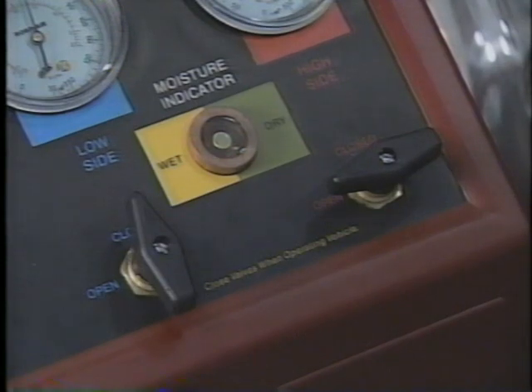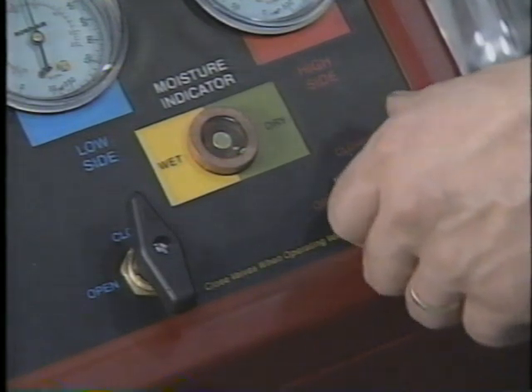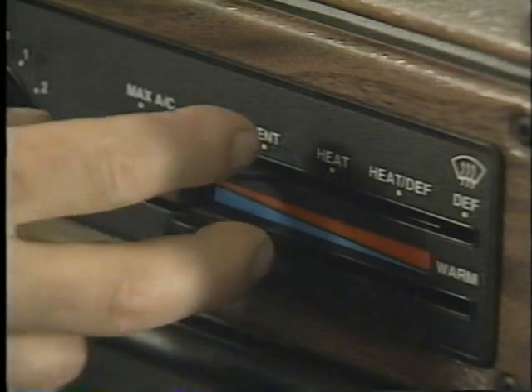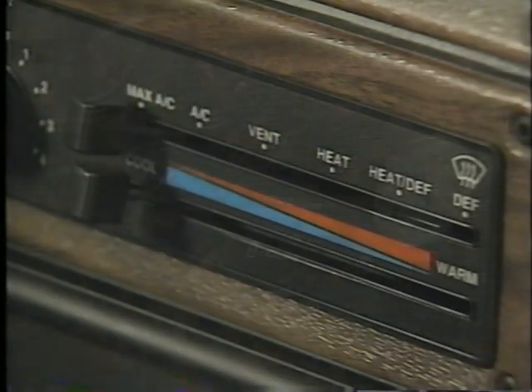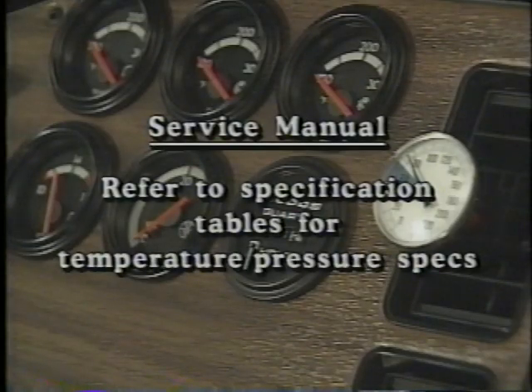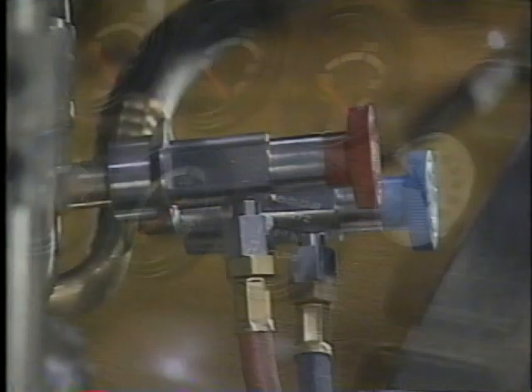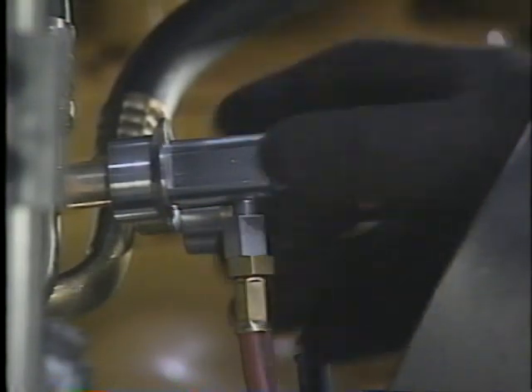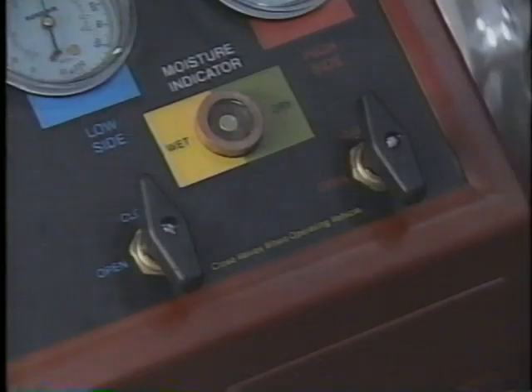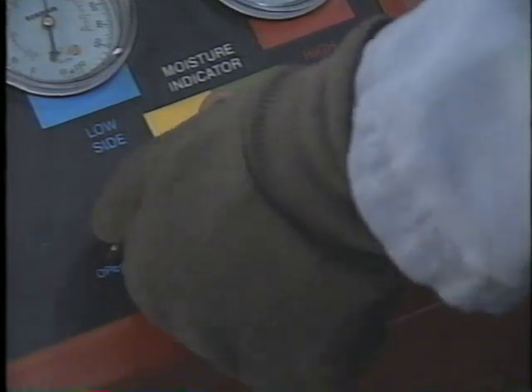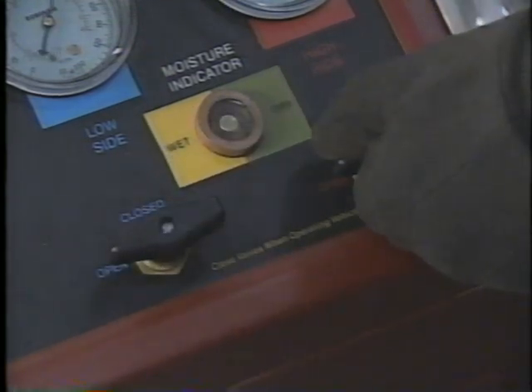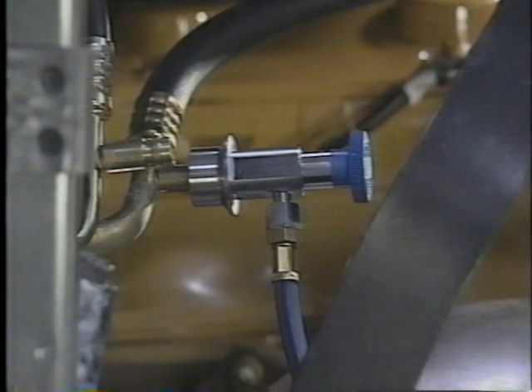When the system is fully charged, close the manifold high-side hand valve. Run the air conditioner at maximum to check the gauge reading and outlet air temperature. Refer to the specification tables in the service manual for the temperature-pressure specifications. Disconnect the red high-side hose and open both valves on the manifold set. The compressor will draw the refrigerant from the charging station lines. Then disconnect the low side.